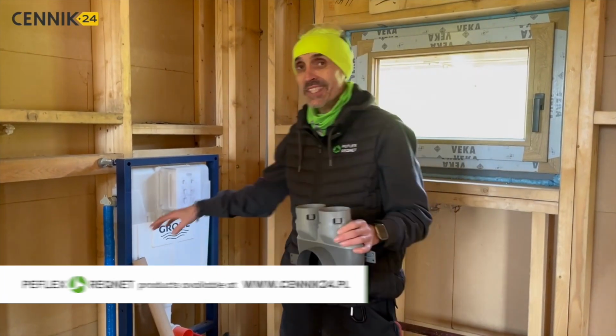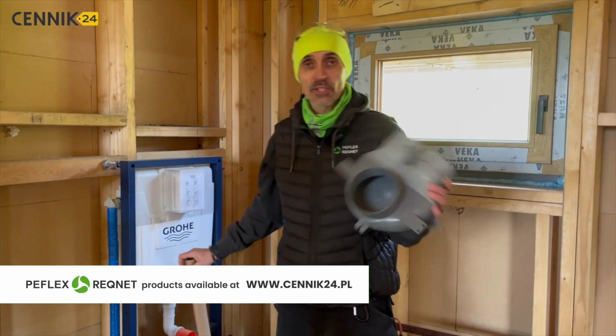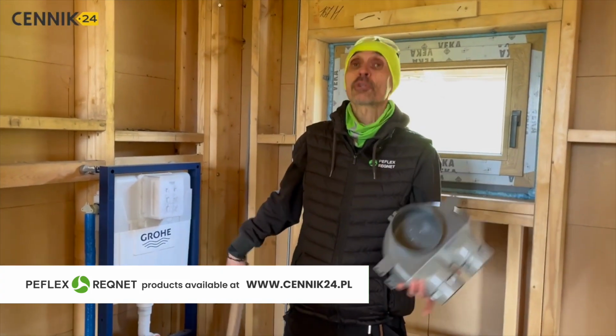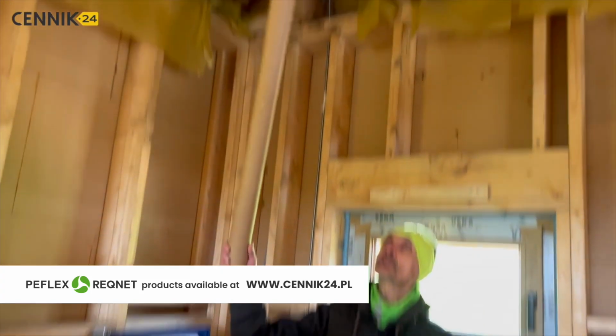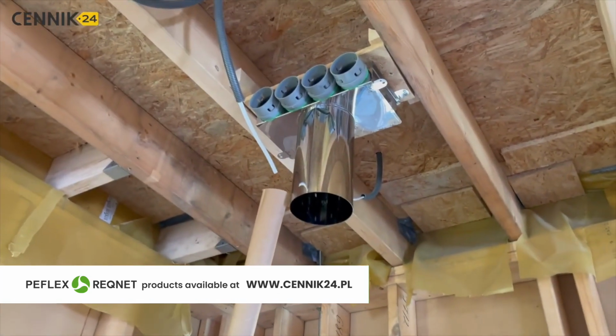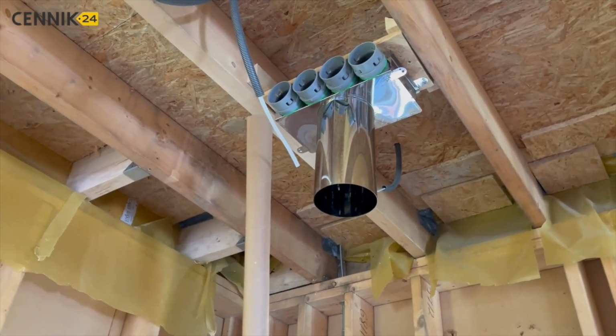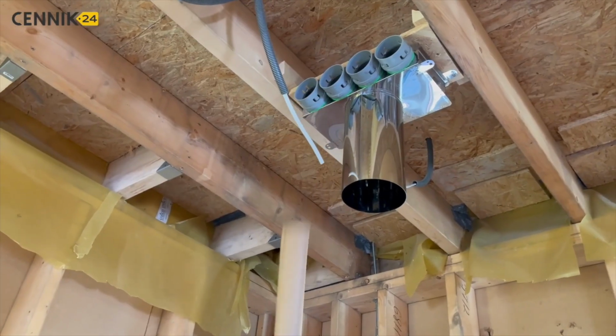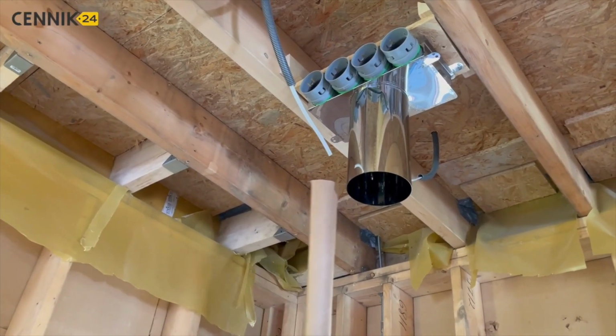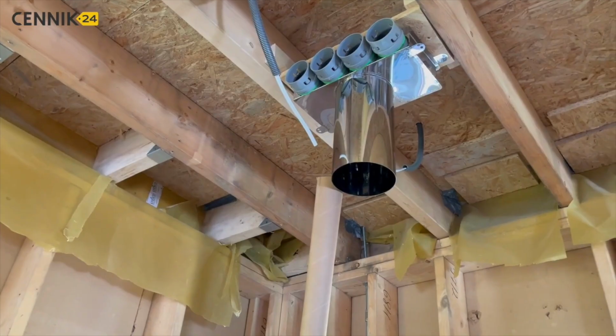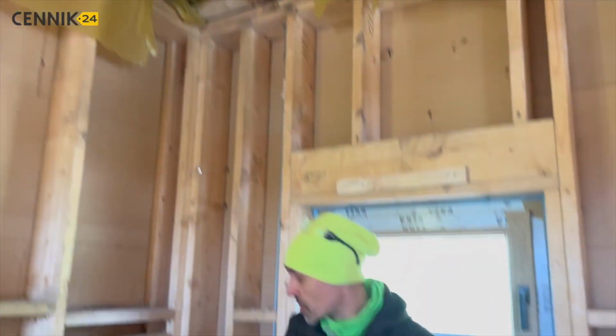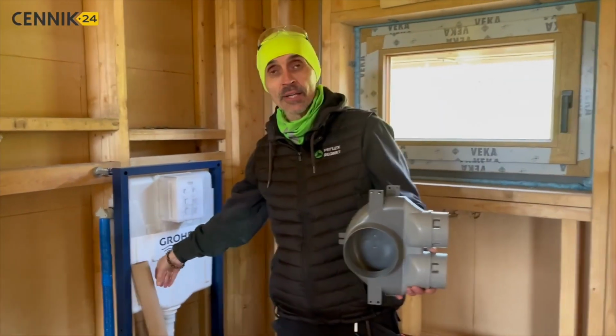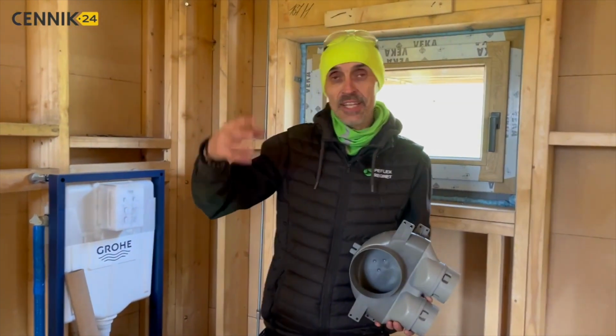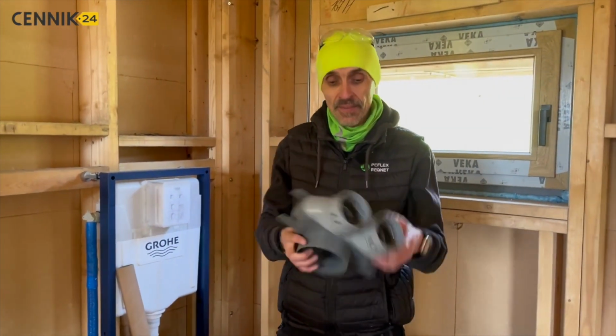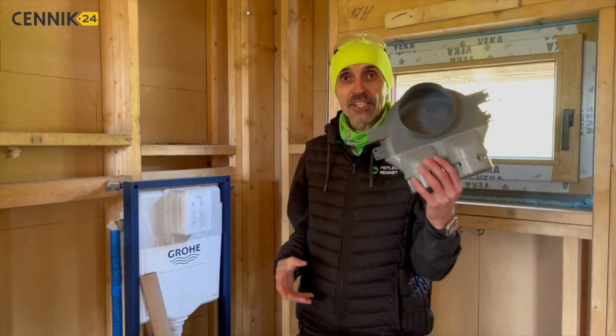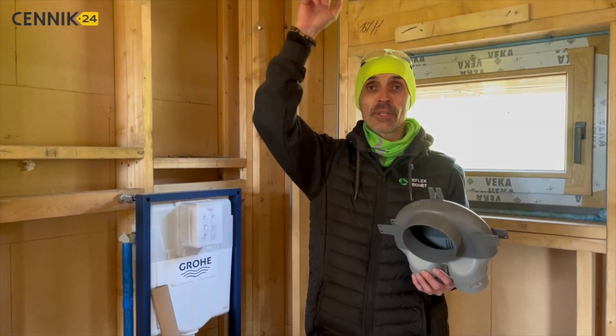However, when it comes to other diameters, such as 100, 125, or 160, we can use metal boxes like this one here, right? Here we have a connection for 4 75mm plastic ducts and an outlet, an approach for a diffuser with a diameter of 160. How does that translate? To achieve the same air output, the same airflow, we can use 2 of these boxes or 1 metal box like this.